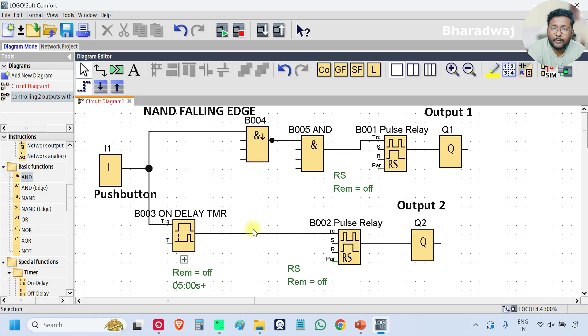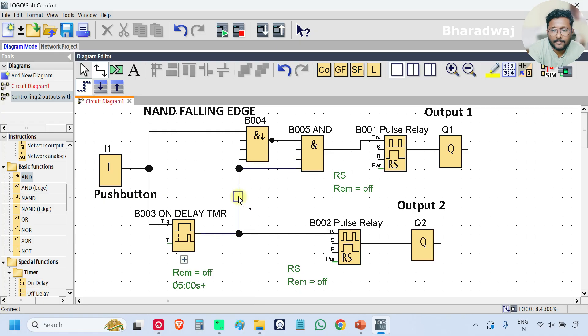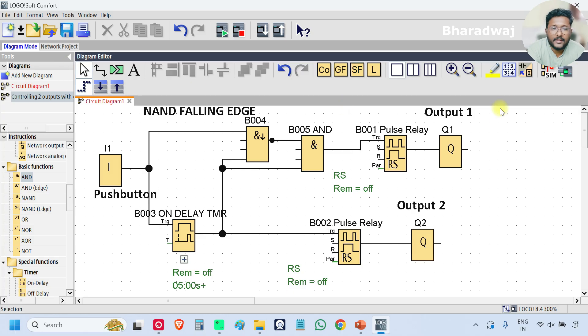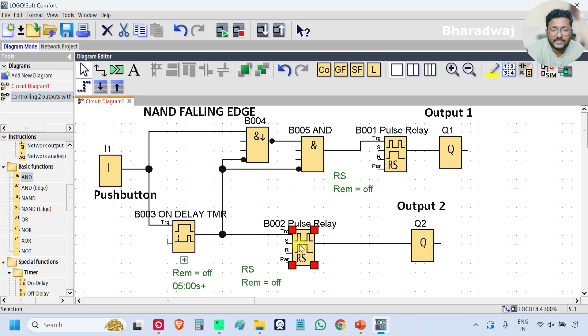Connect the output of the on-delay timer to the last input of the NAND falling edge block, and similarly connect the on-delay timer output to the fourth input of the NAND block. Now add NOT inputs — double-click on the line and a bubble will appear, meaning NOT is added. Add NOT on both inputs. The program is now completed.